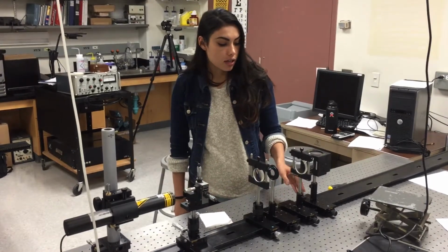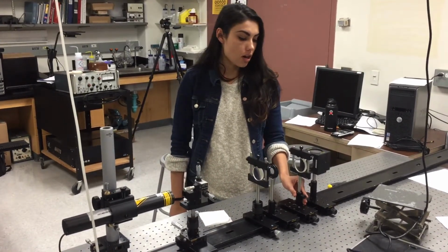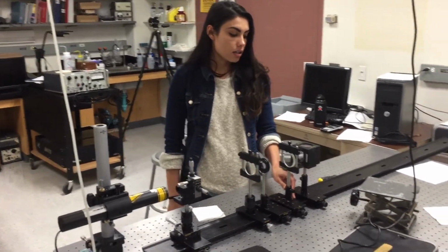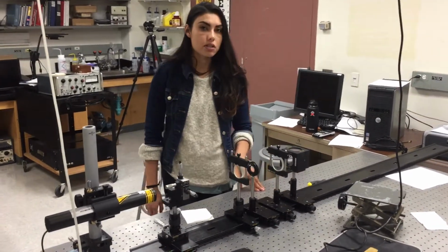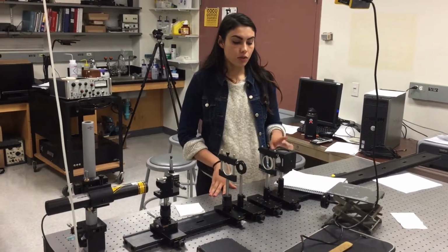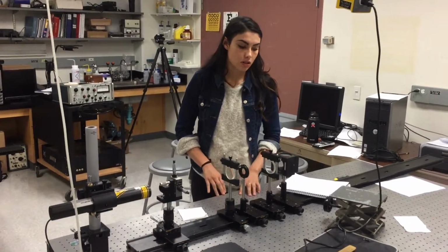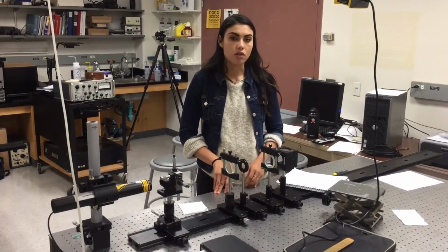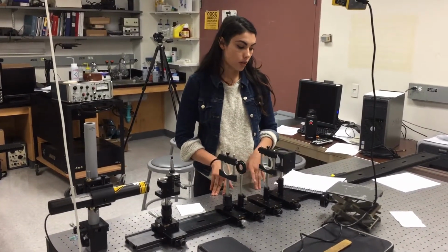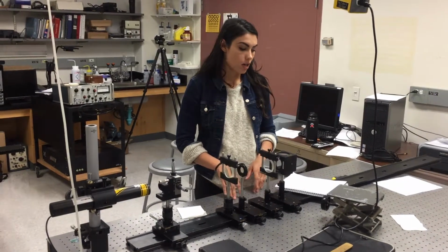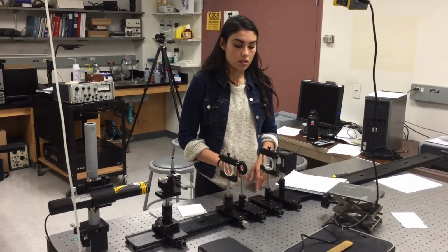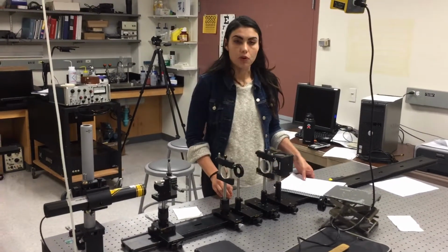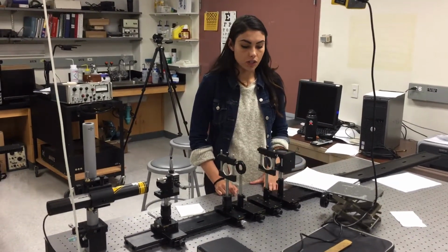We placed a test lens in between our expander and our shear plate, and then we were able to see the profile. Our shear plate allows us to measure the wavefront of different optical elements, and we can physically measure our fringe orientation, our shear distance, and our fringe spacing. From this, we can calculate the radius of curvature of these wavefronts and find the focal lengths of the optical elements that we're looking at.